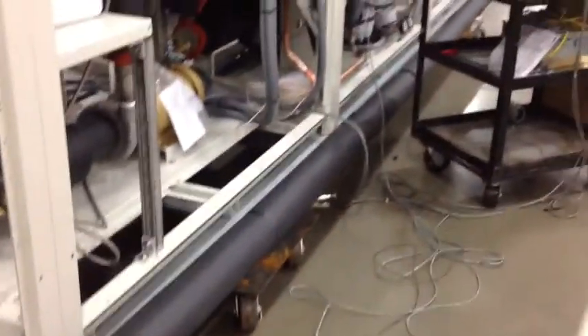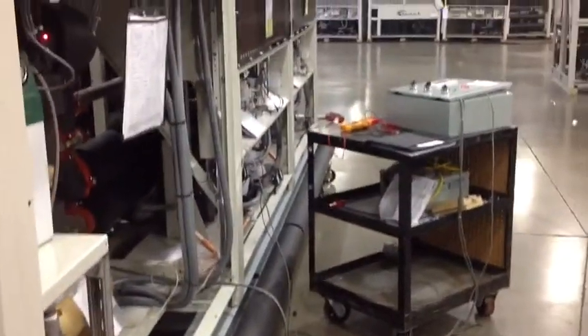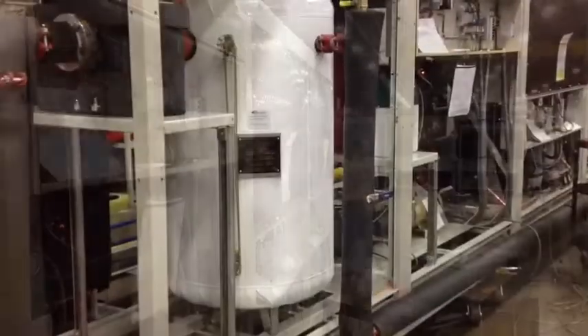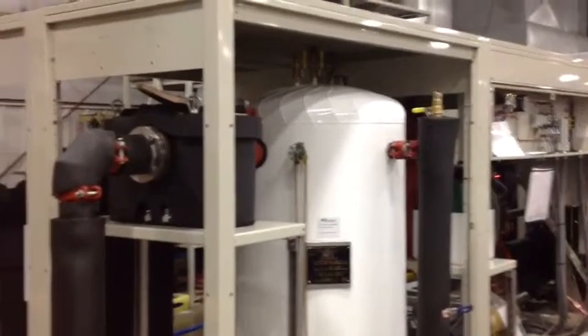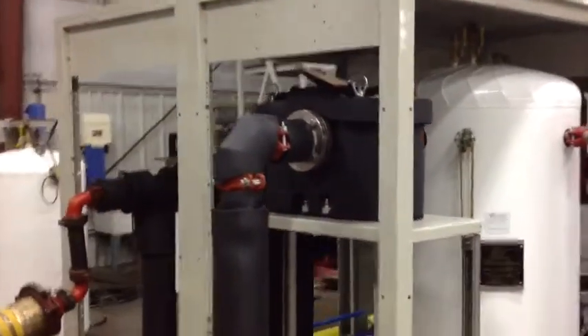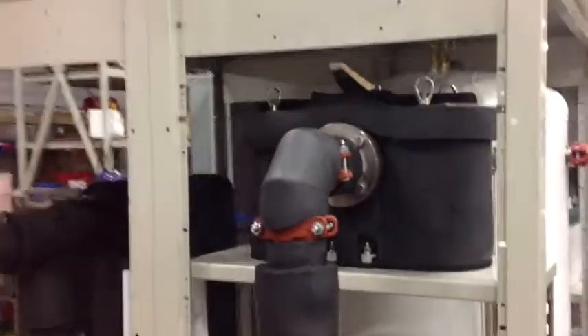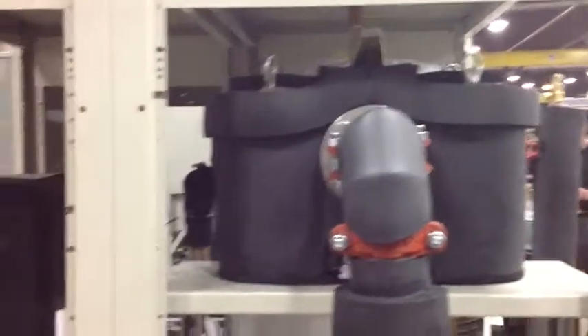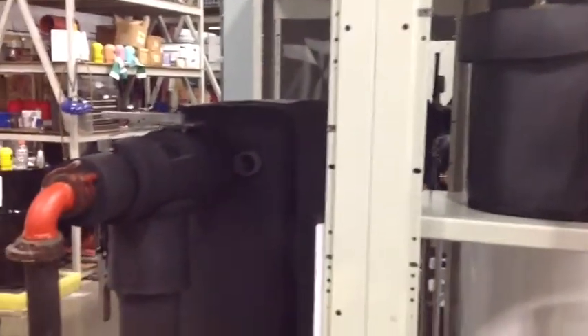As we pan down, you see the insulated pipe running along the bottom of the lifting frame. That is the bypass line. There are a set of balancing valves that will control the flow of any excess water instead of to the building, back to the storage tank. So the building only receives the precise amount of water that it needs.